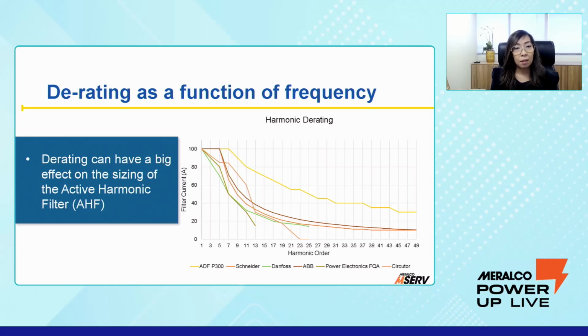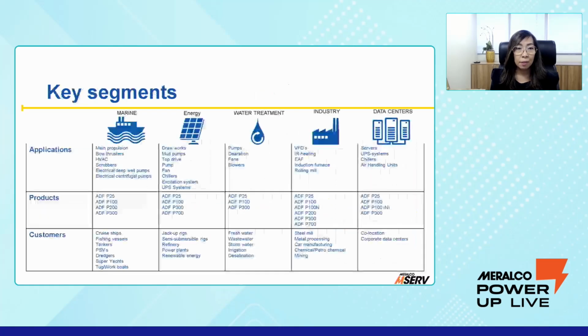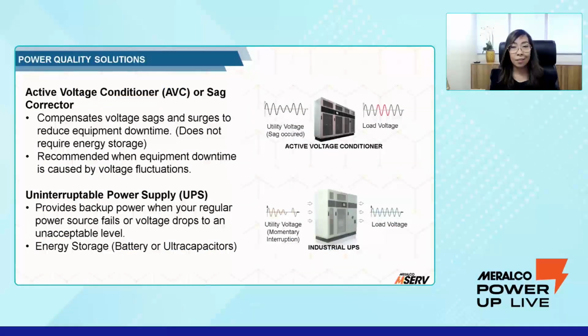Why is it very recommended by MServe? If you look at the graph, at 7, they're all equal, all of the different brands. But as you move towards the right, the other brands are derated. So the efficiency of the ADF system is actually quite good. So it can be used for the different segments, for marine, energy, water treatment, industry, and data centers. So after a thorough PQ study, we will size the active harmonic filter for you and recommend the proper sizing.